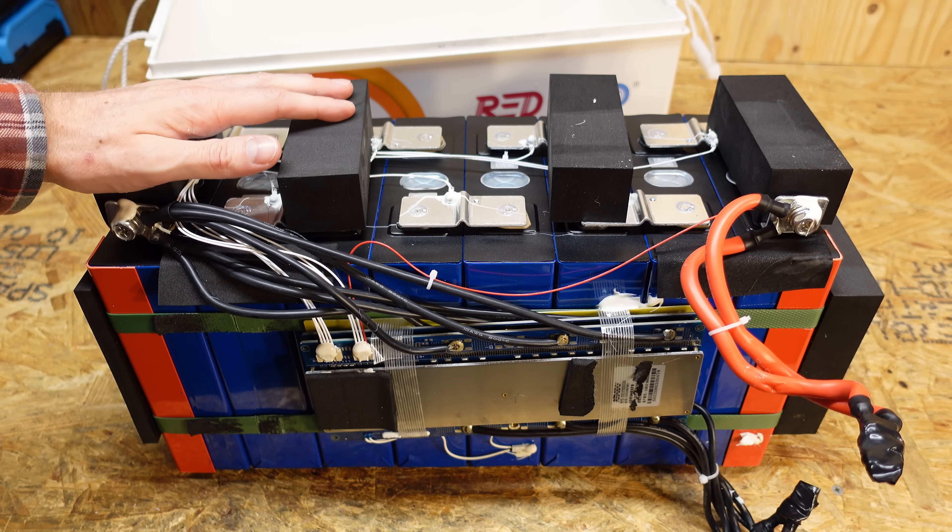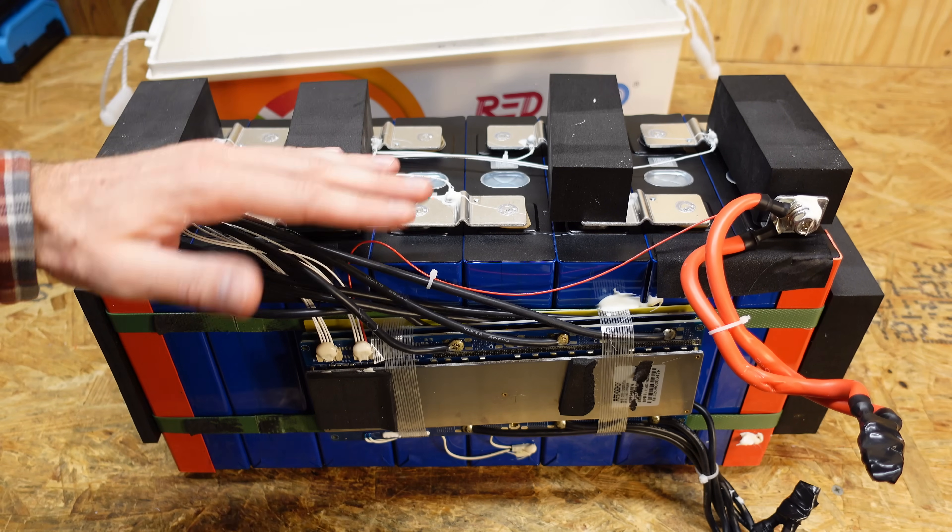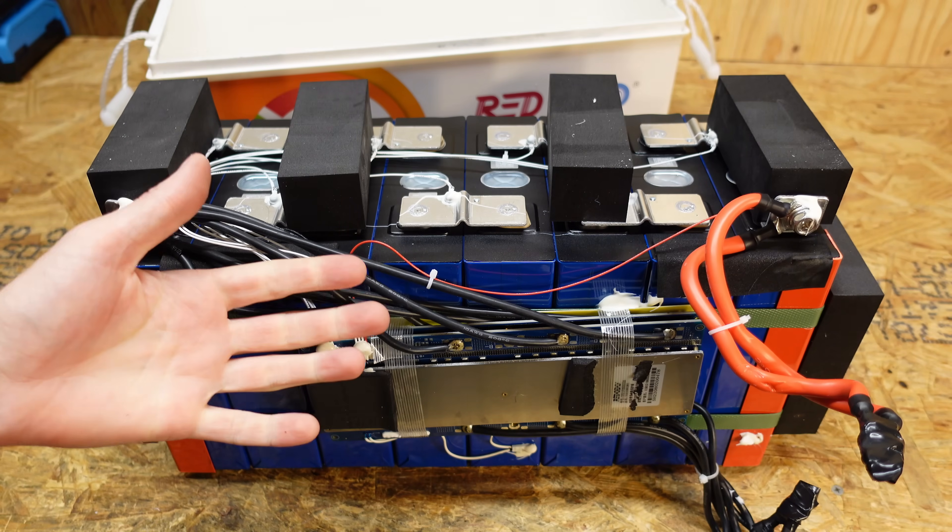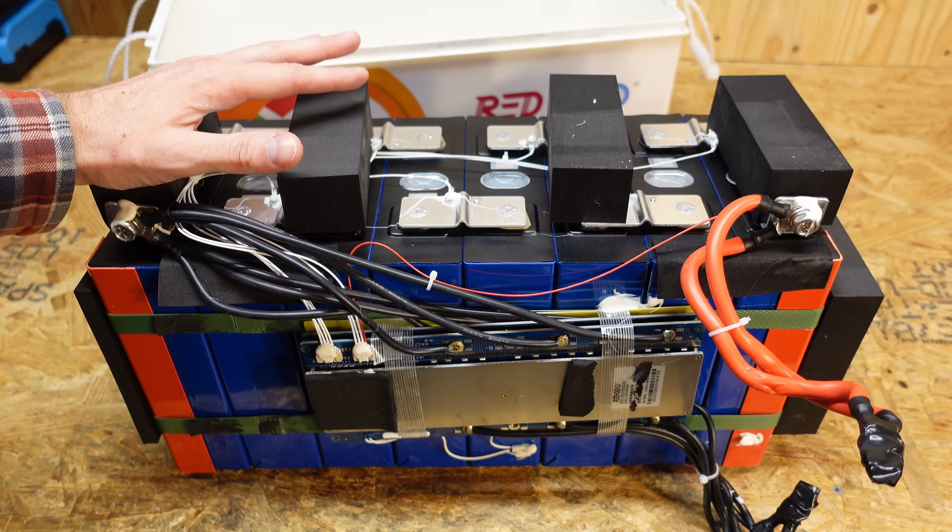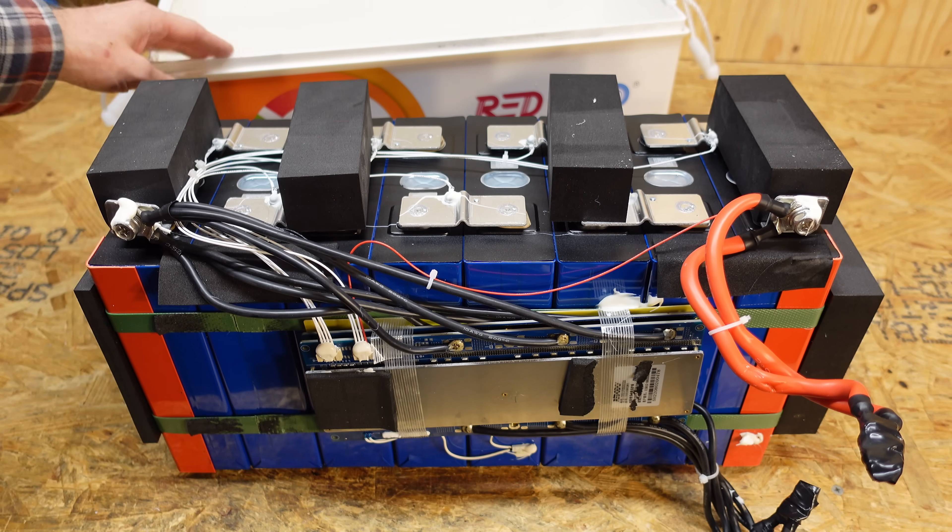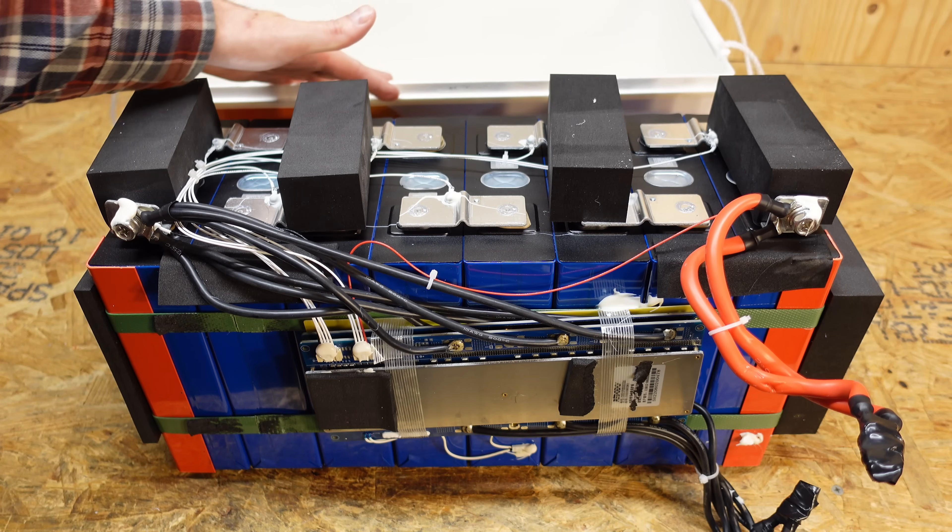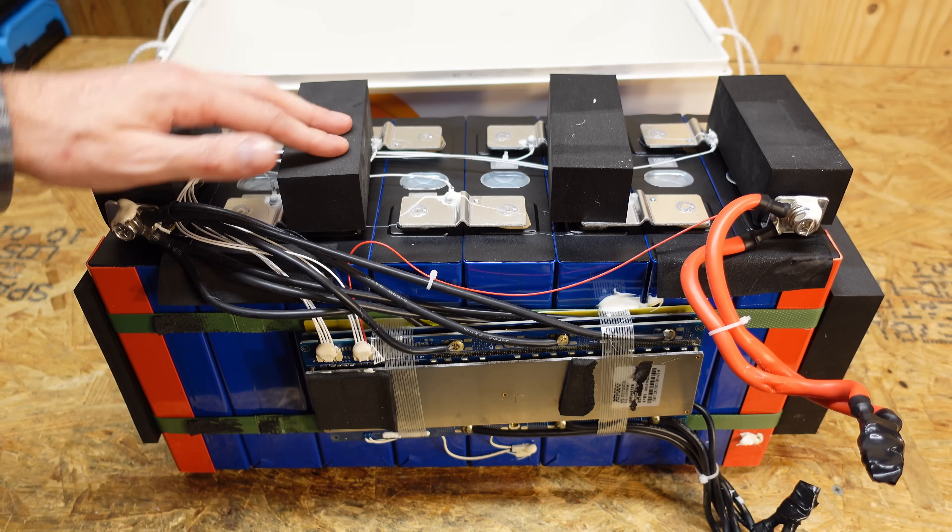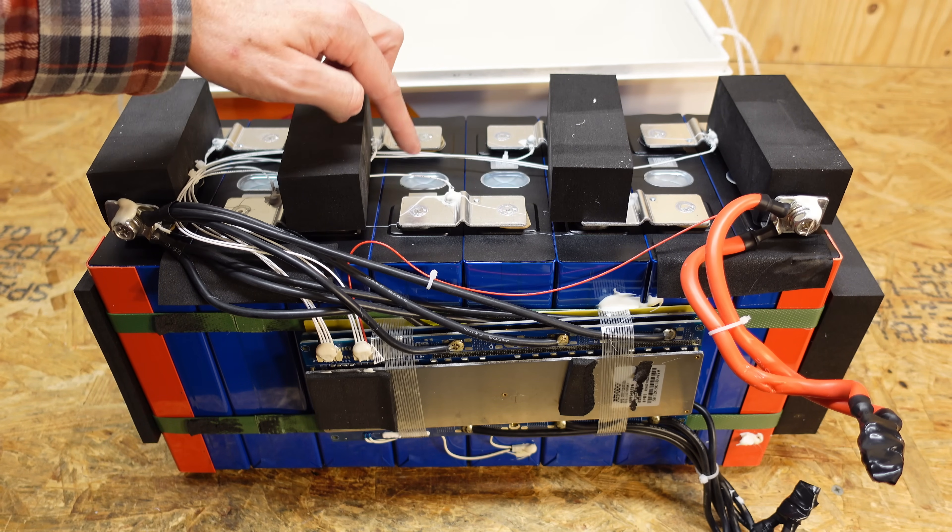So one thing that immediately came to my mind as I was pulling this out is that the battery was on its side while the battery was oriented upward. So the documentation says the battery could not be upside down per the posts of the actual case. But one of the side orientations would actually have these terminals facing down, and that is not good.